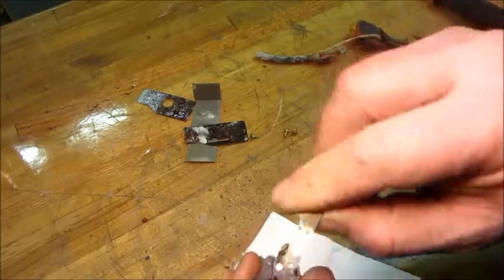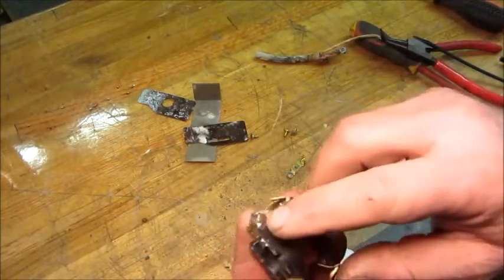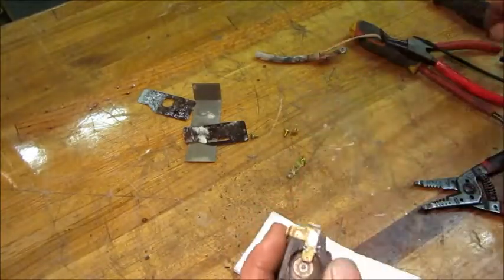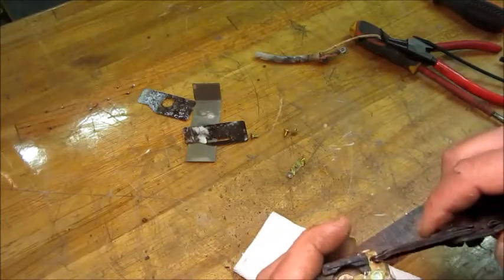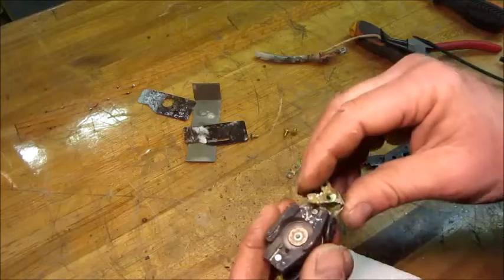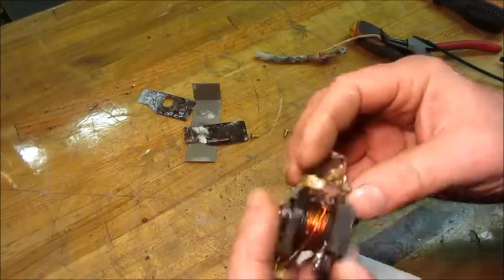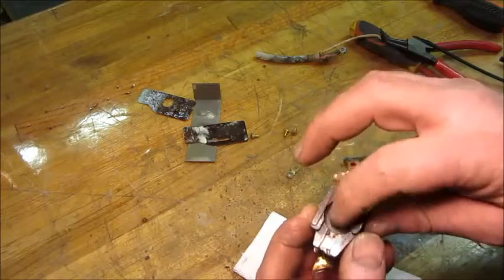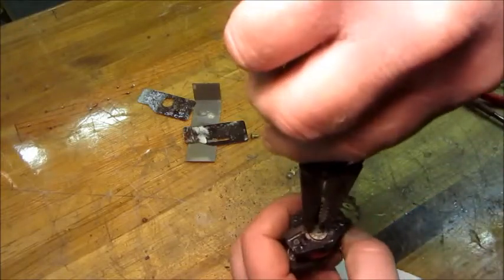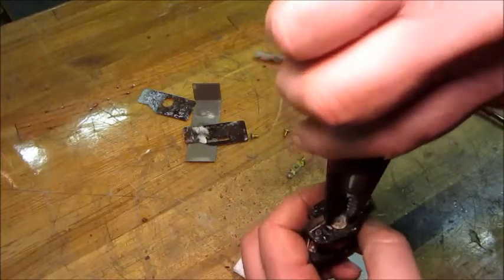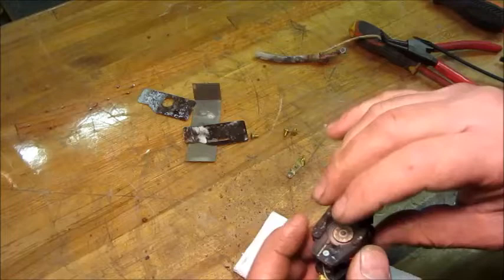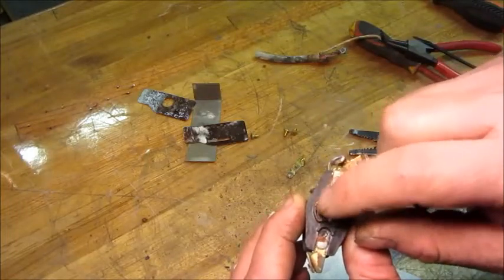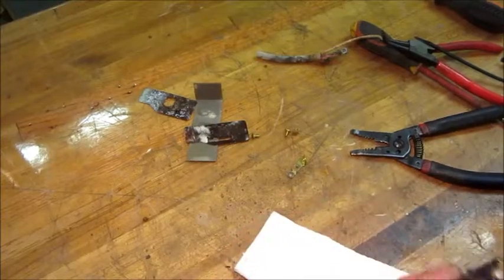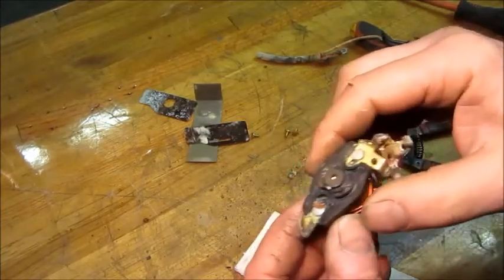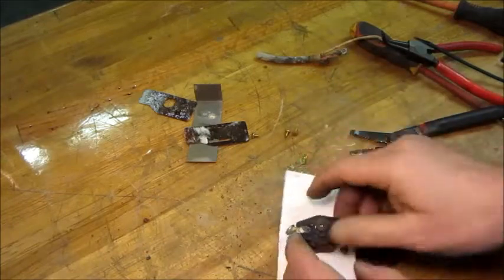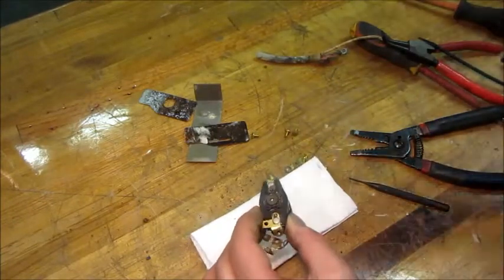Alright, rivets are gone. Take these start contacts off. This one's soldered into the series coil. This is the common input. So that one, I'm just going to leave it hanging like that rather than worry about desoldering and resoldering. And now let's see if this will pull out of there. Nope, it won't. Rather than break the plunger or something in there, I'm going to do like I did the last one, drill a little bitty hole in the center of that where a hammer and punch can be used. Okay, got a little hole drilled in there. That's got plenty of room to slide out before it hits the table.